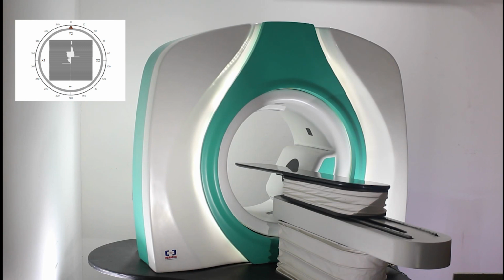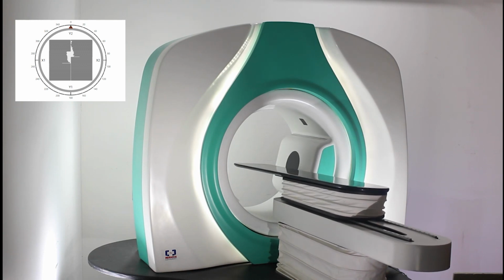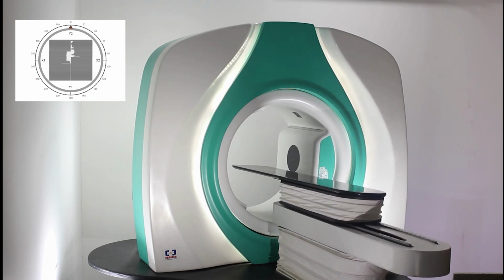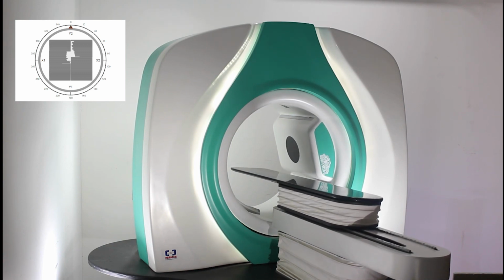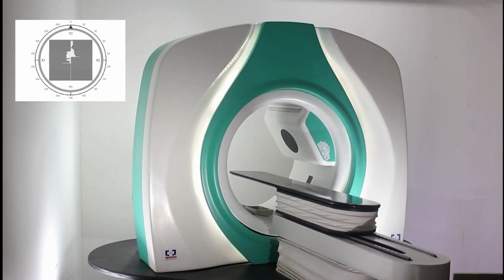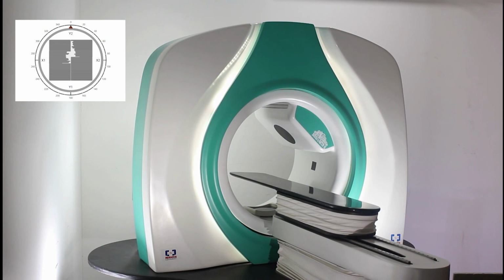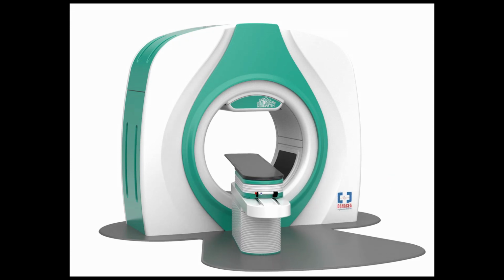The precise dynamic MLC with leaf thickness of 5 mm at ISO center and 10 mm across the bank and speed surpassing 3 cm per second along with the dynamically varying gantry speed and variable dose rates enables it to deliver a wide range of dose fluence to the targeted volume. A unique feature of having couch isocentric rotation on a ring gantry platform enables non-coplanar treatments.